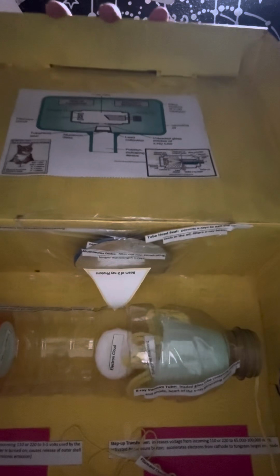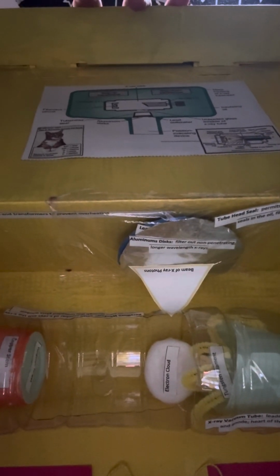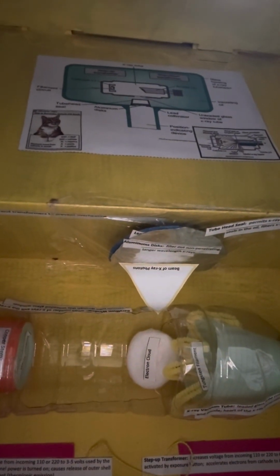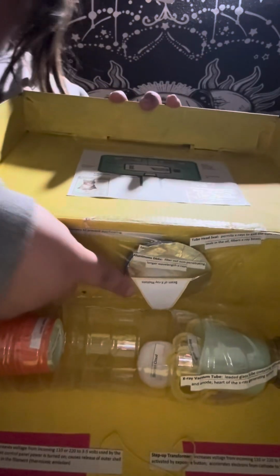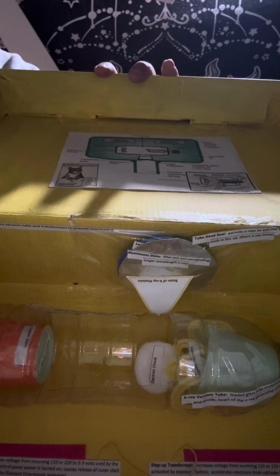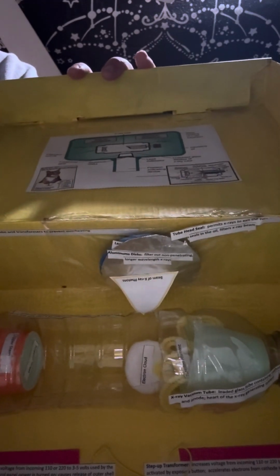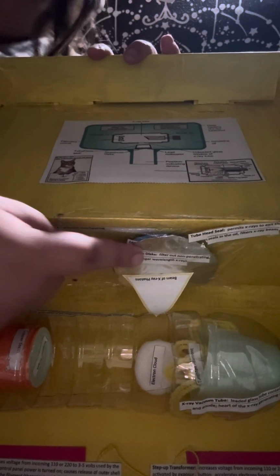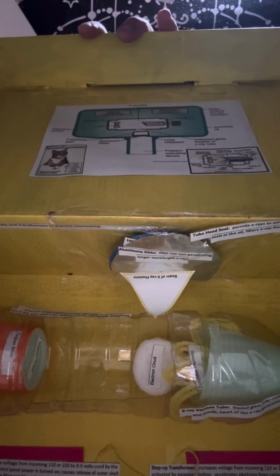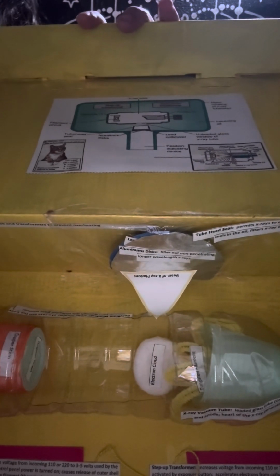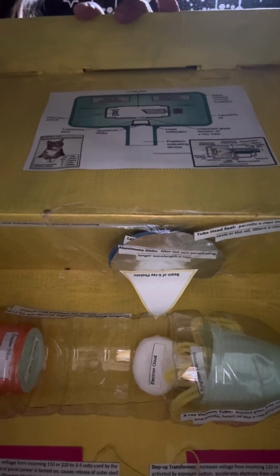And now we'll open the inside of our box again. So this is the inside of our tube head. As you can see, all the yellow around the inside of the tube head is our insulating oil. Our insulating oil surrounds the x-ray vacuum tube and the transformers to prevent any overheating. Next is our tube head seal, which is down here. Our tube head seal permits the x-ray to exit from the tube head. It seals in the oil and helps filter the x-ray beam. Over the seal is our aluminum disc, which helps filter out non-penetrating longer wavelength x-rays. And under that is our lead collimator, which restricts the size of the x-ray beam.